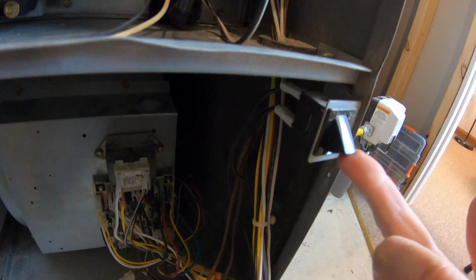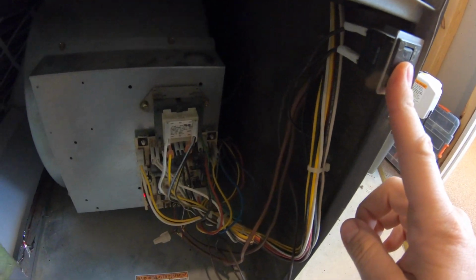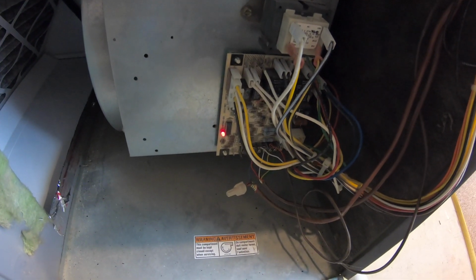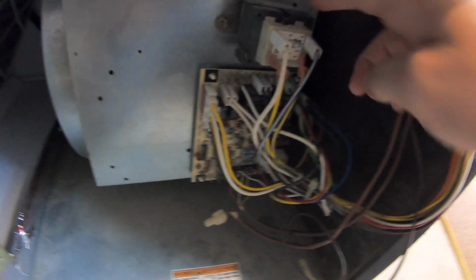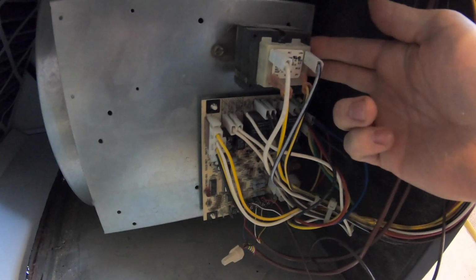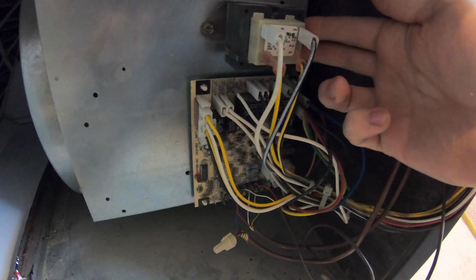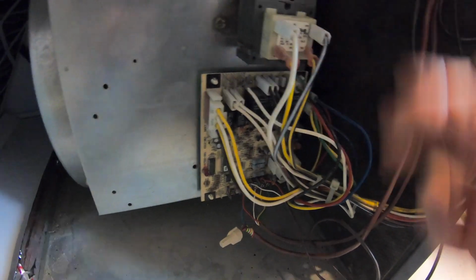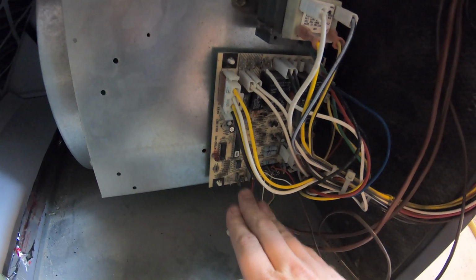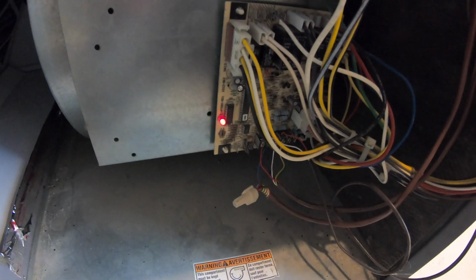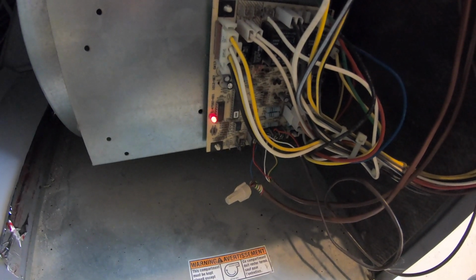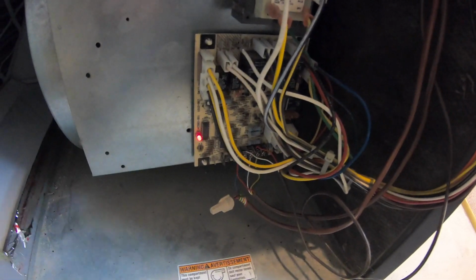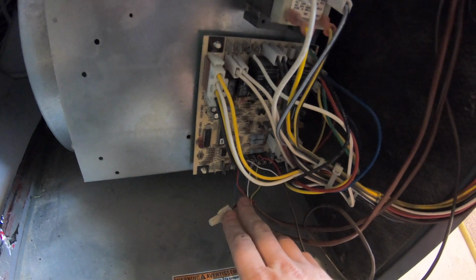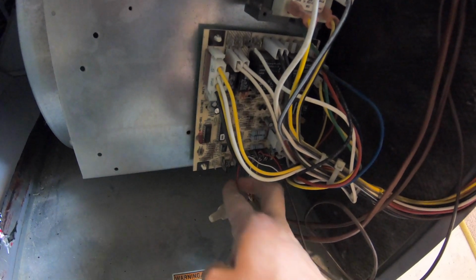And there is a blower door switch. If I push this blower door switch in, then power comes on to my circuit board and this transformer here. So this transformer converts the voltage from 120 volts AC to 24 volts AC to power this circuit board and all the controls. Now you notice that LED light comes on. That is a status indicator light that will tell us if there's a problem with the furnace, and we'll get into that later.